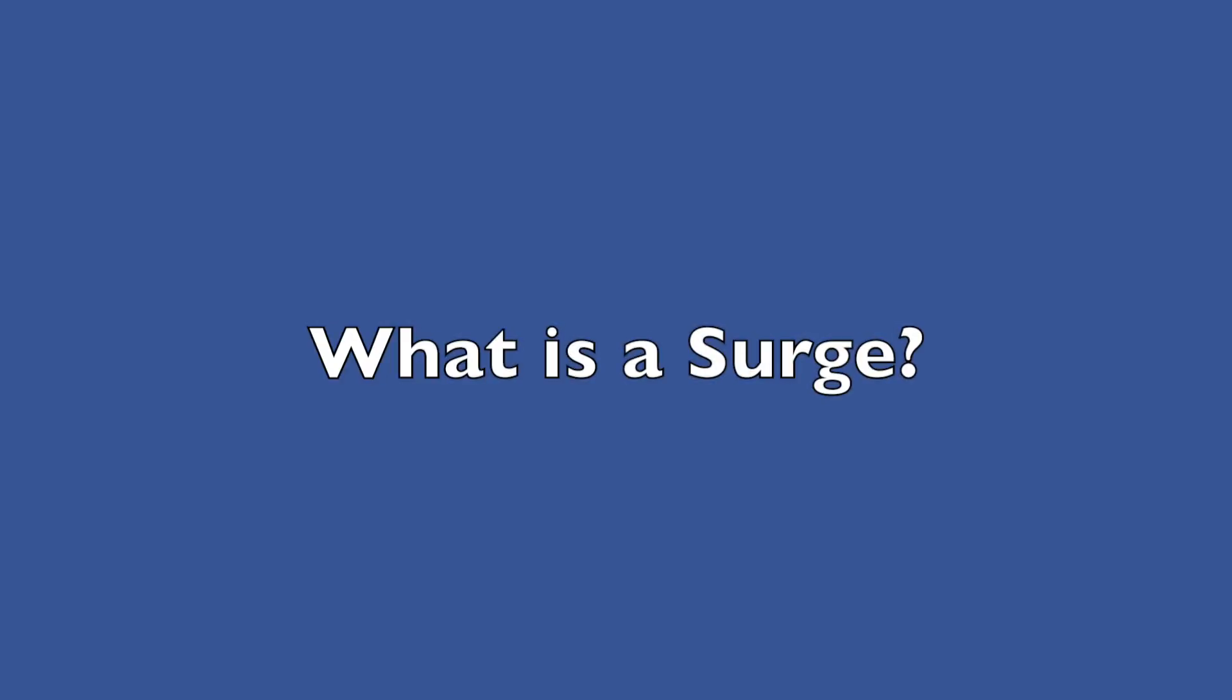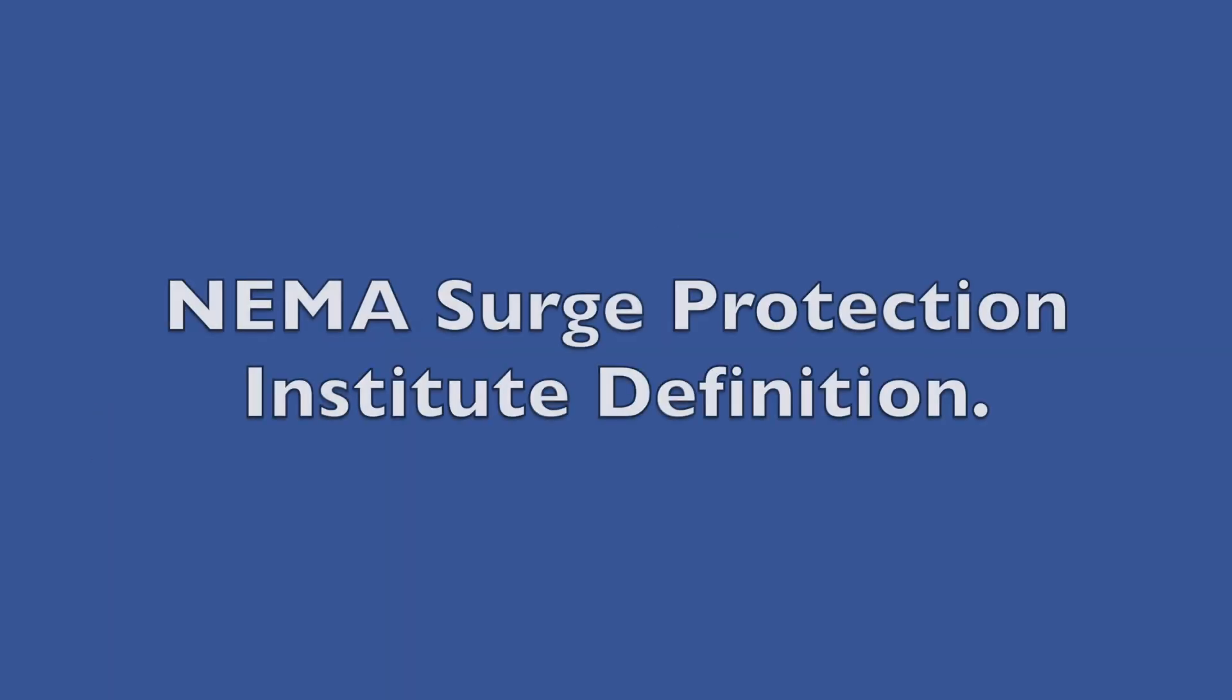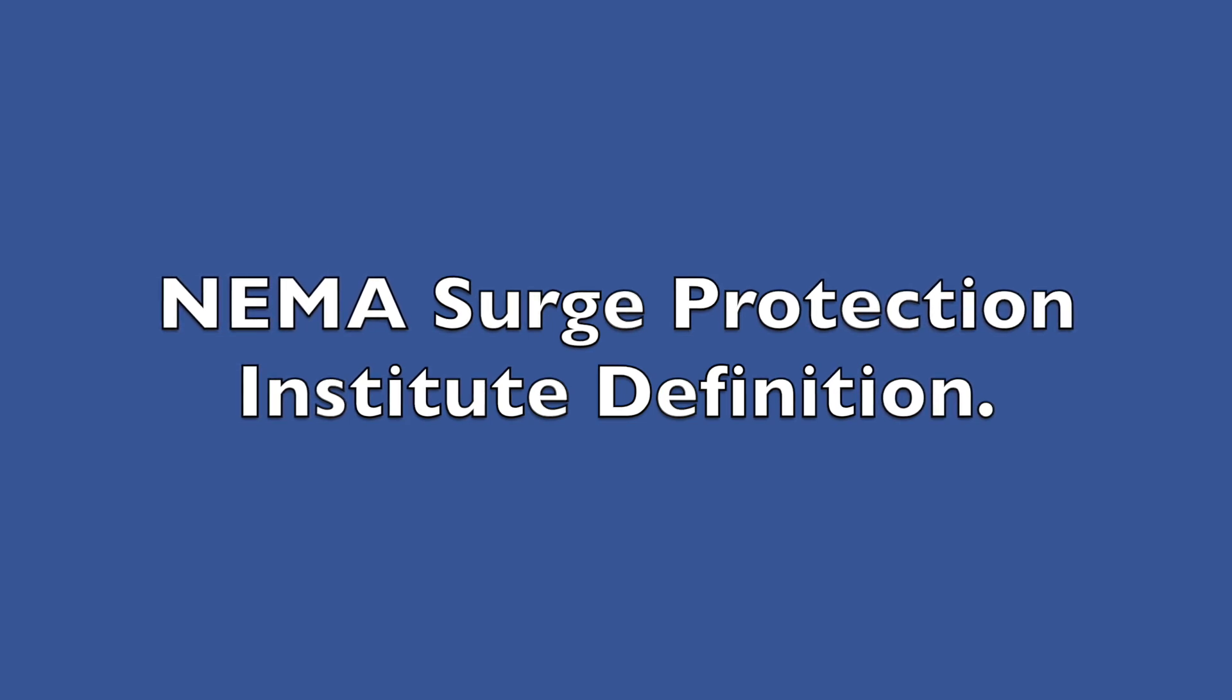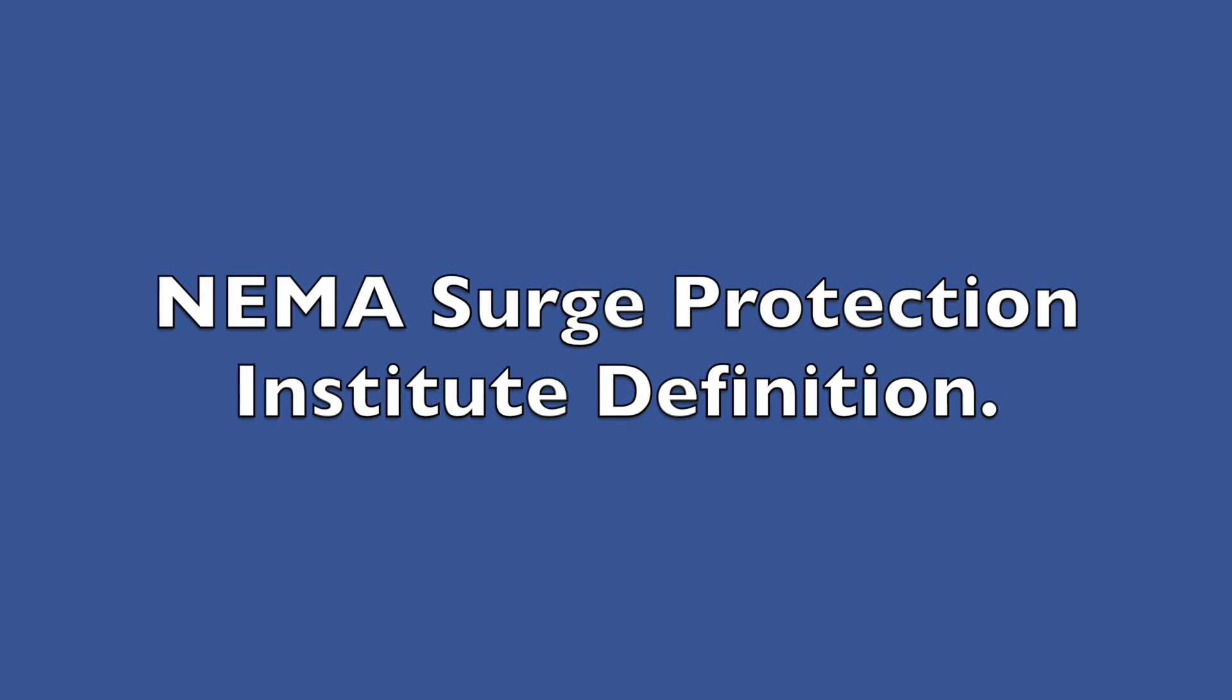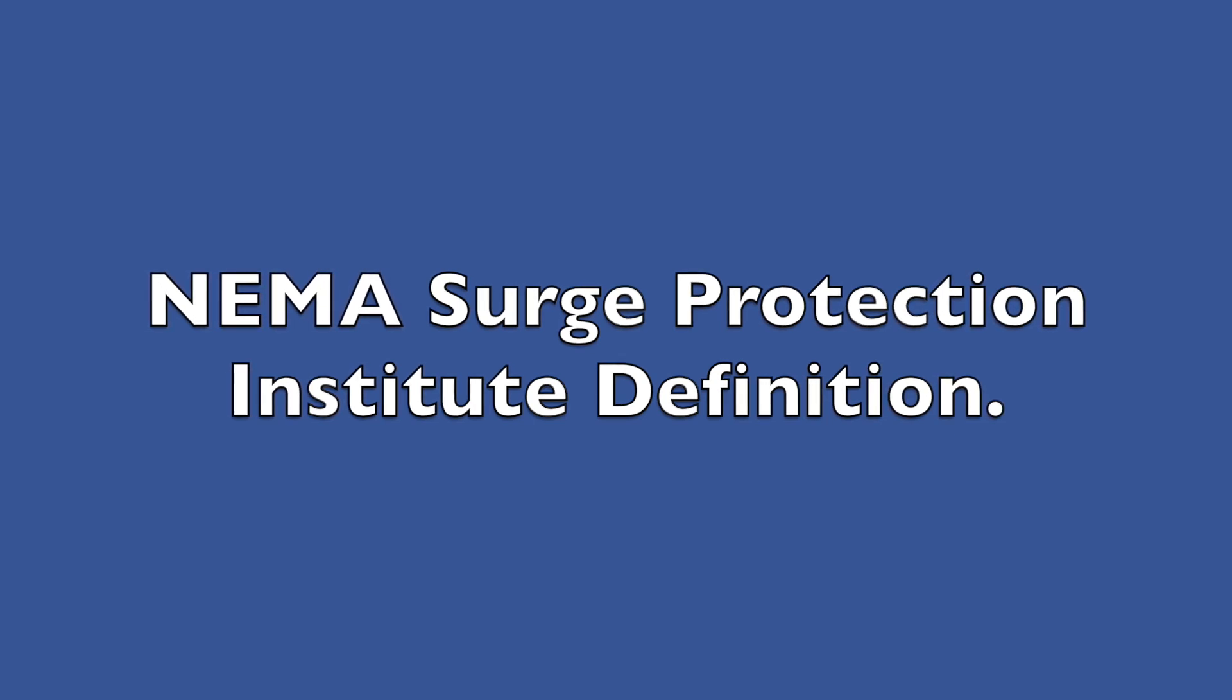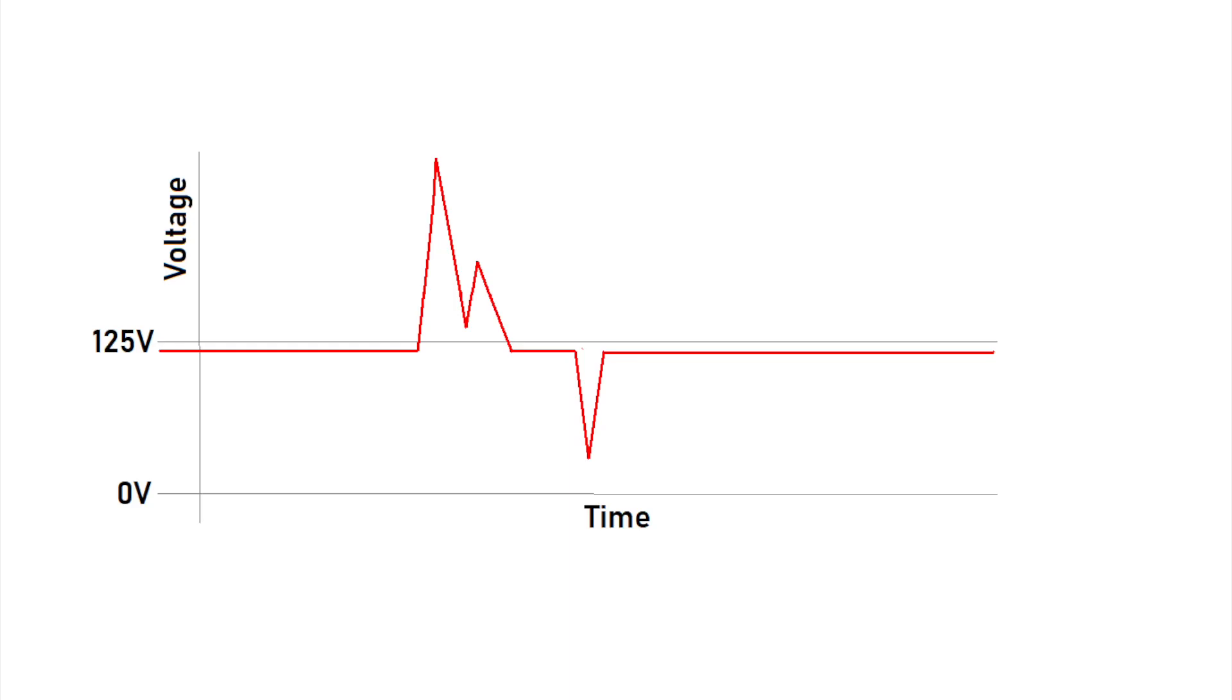What is a surge anyway? The NEMA Surge Protection Institute states a surge or transient is a sub-cycle overvoltage with a duration of less than a half cycle of the normal voltage waveform. A surge can either be positive or negative polarity, can be additive or subtractive from the normal voltage waveform, and it is often oscillatory and decaying over time. What does that even mean? Basically, it is an abnormally high voltage spike that can damage your equipment.